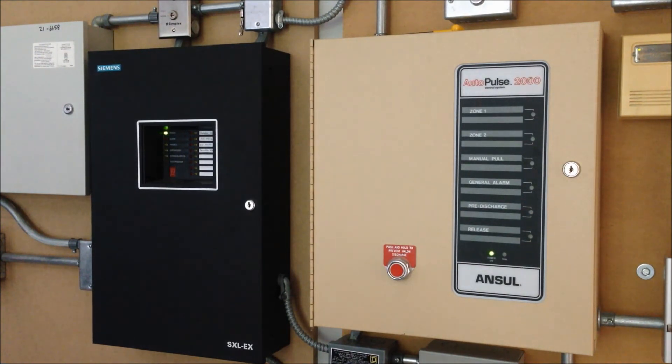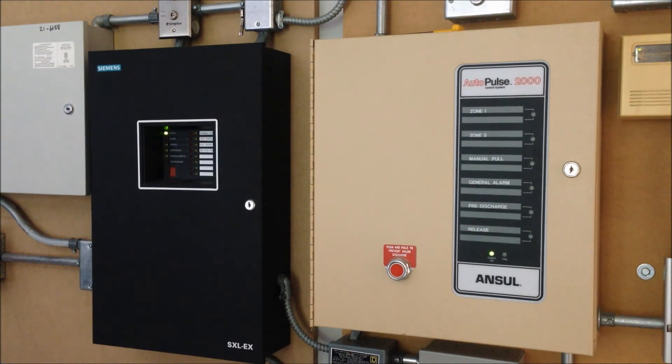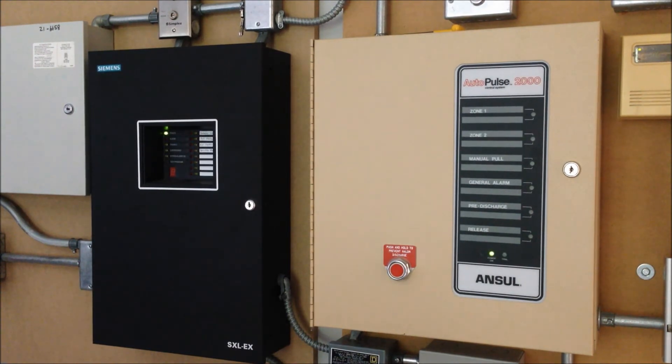As you can tell by the two green indicator LEDs and no trouble LEDs, I now have standby SLA batteries installed in both of these panels, so let's go ahead and take a closer look.